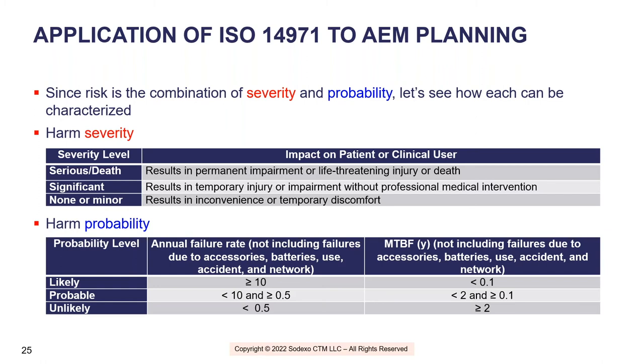These are not failure rates for accessories. So is the equipment broke if an EKG lead wears out? Did the equipment break? If a finger sensor goes out, did that monitor fail, or was it an accessory? You're right, however, the device still isn't broken, it's just got a bad accessory. So we're looking at true failures.